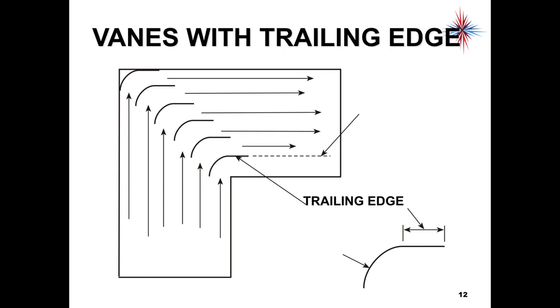So we hit the turning vane, we have a 90-degree bend multiple times through the corner there. You'll see how they're mounted there. All the air has to pass through, but it's basically allowing straight lines. We don't have the air mixing, we don't have the air hitting any dead corners, and we're basically throwing the air around the corner. That's one way to not have any pressure reducing. It helps the dynamic loss.